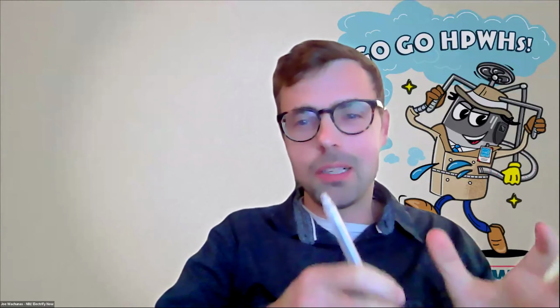Yeah, I can speak to that too, Greg. We have our heat pump water heater in our utility closet right near our living room, and for years we had it ducted. Then we did a remodel and decided to try without the ducts. We took them off, and since it's in a closet, we put some wall grates, so it's pulling air from behind the fridge and going into the pantry. You can also do a louvered door, like Greg mentioned. It runs 6 to 8 hours a day, it's cooler in the winter, but nothing dramatic — really a nothing burger from my perspective. And in the summer you get that free AC. But that's only for about 25% of homes that have a utility closet like mine with the water heater in it. Most homes have it in basements or garages.